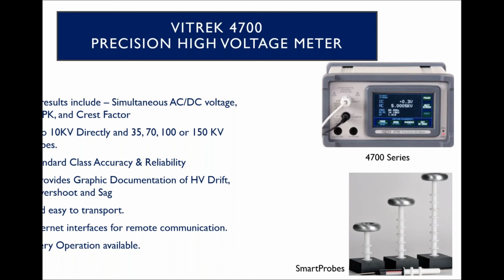They're used in labs around the world, as I said before, and listed on quite a few scopes of accreditation. It does have a chart mode, which allows you to graphically view your voltage over time. It really helps you gauge ramp times, lets you see things like overshoot on ramp or turn on, and sag throughout, depending on loading. It is lightweight, easy to transport. It's a little under 3U tall and a little less than half rack width. And I believe it's about 7 pounds.